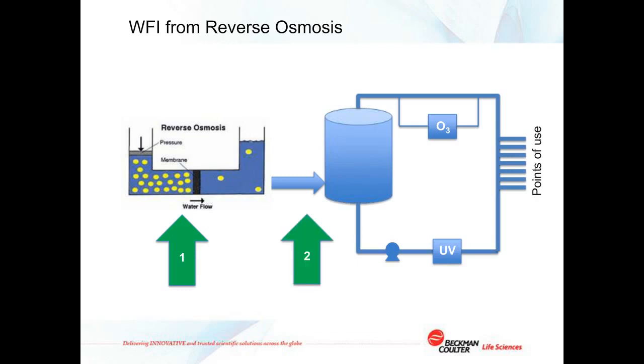Water made through the reverse osmosis process is manufactured at ambient temperature and does not require high energy input to heat it. A study done by a working group from the pharmaceutical industry and water system suppliers under the auspices of the International Society for Pharmaceutical Engineering, the ISPE, resulted in the publication in 2012 of the ISPE Guide on Ozone Sanitization of Pharmaceutical Water Systems, which recommends the advantages of ozone sanitization and lays down best practices.